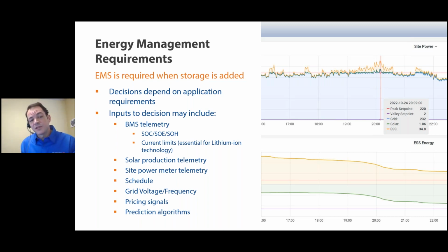When the EMS is making decisions, it's pulling data from a lot of different equipment on the site. For example, the battery management system provides information on the battery, such as state of charge as well as charge and discharge current limits. It also pulls information from your solar array on how much power is coming out, and it talks with power meters to get data on the AC meters of your loads, as well as configuration information like what schedule is loaded and what energy application is being used.